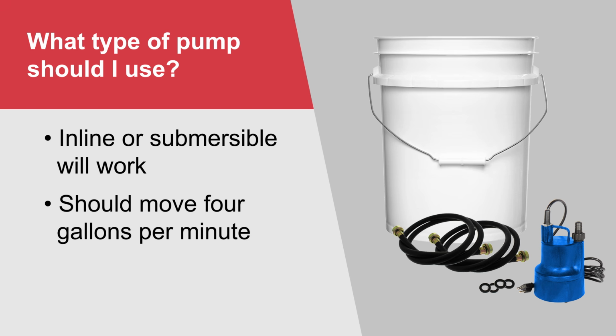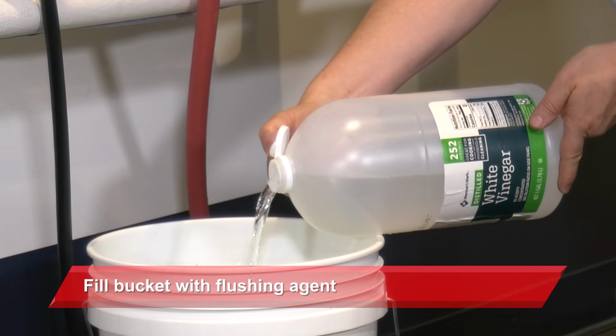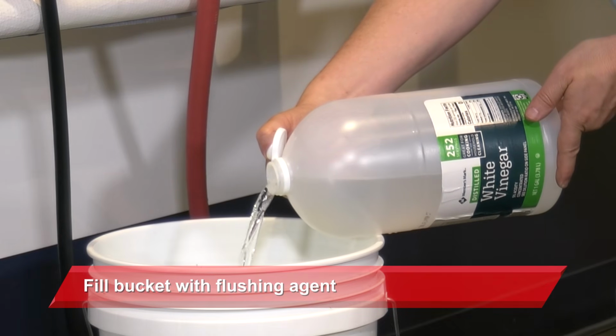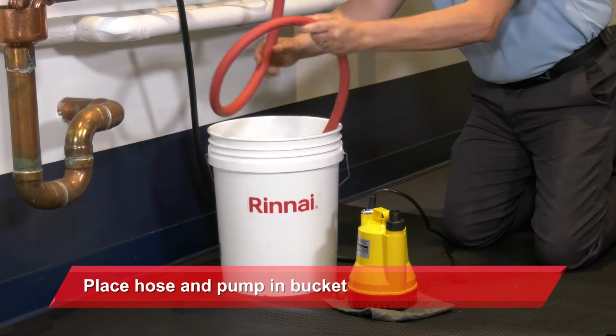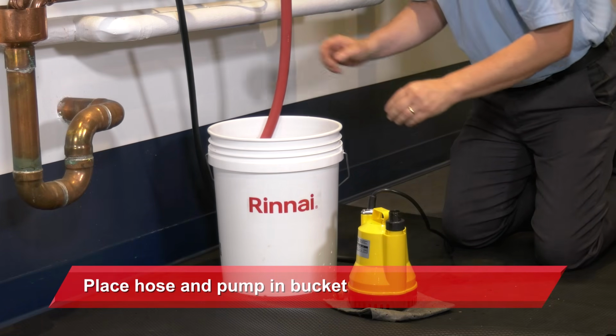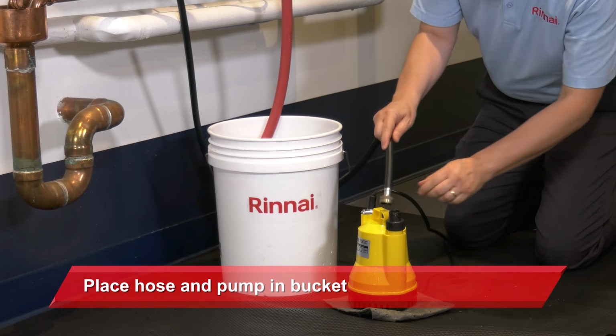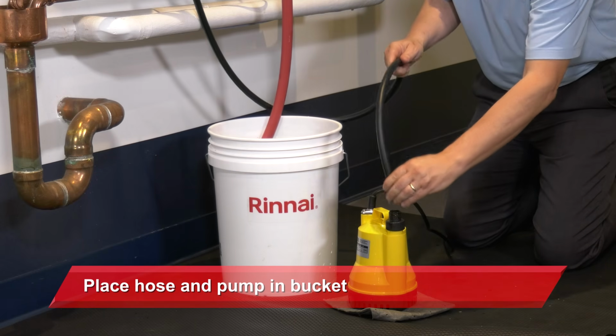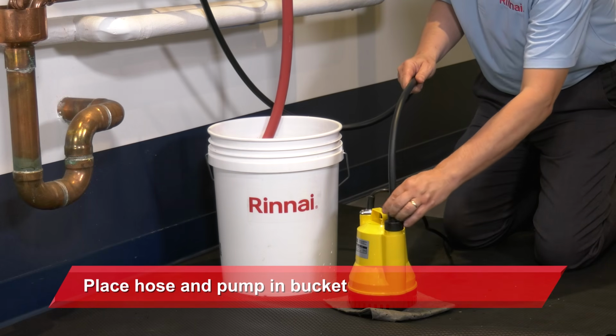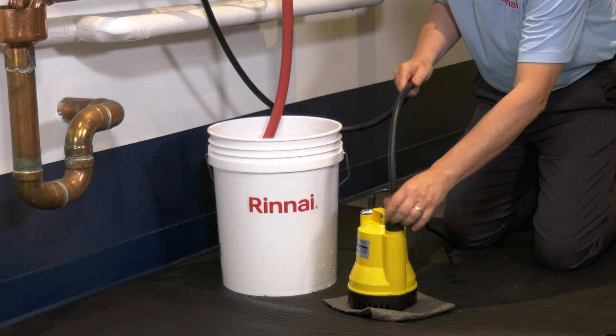The pump should move about 4 gallons per minute of liquid through the water heater during the flush. In most cases, a 1/6 horsepower flush pump should work just fine. We're going to fill a 5-gallon bucket with 4 gallons of flushing agent. And we're going to place the hose from the hot side isolation drain valve to rest inside the bucket. And the hose from the cold side will connect to the top of the pump, and we'll place it inside the bucket as well.